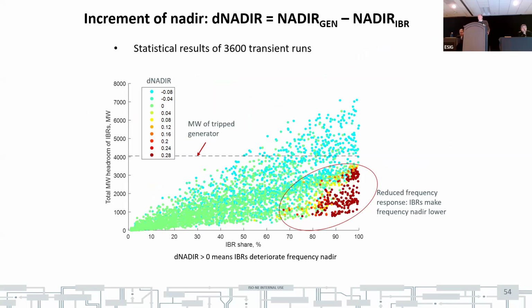Okay, and this picture shows results of a statistical run. Every dot on this plot is a single transient calculation, and color-coded points show deviation of nadir compared to the case when you have only generators. So a reddish color means that IBR deteriorates the nadir of frequency. And from this plot, for this calculation, only grid-forming inverters were modeled in the system. And the horizontal line in the graph shows percentage of IBR penetration. So all negative results, which are highlighted reddish, are located in the area where you have a lot of IBR with relatively small headroom for control. That is the main conclusion.